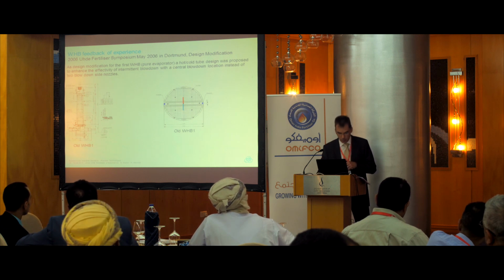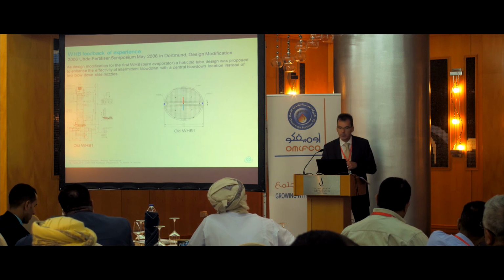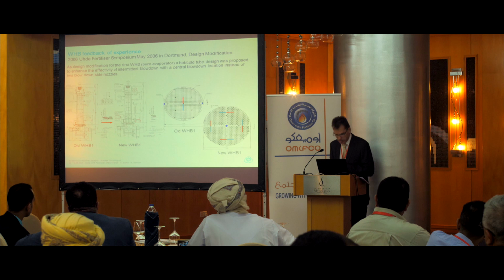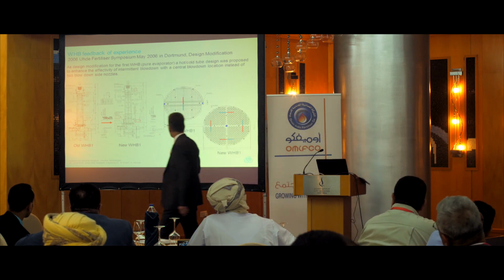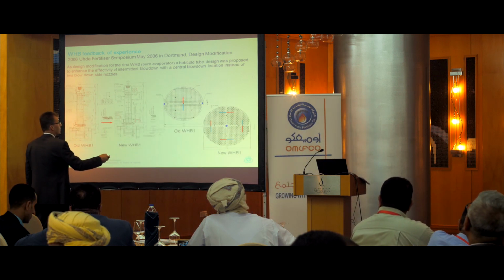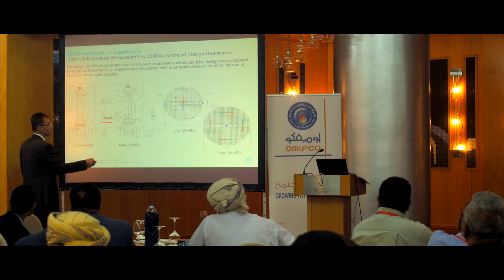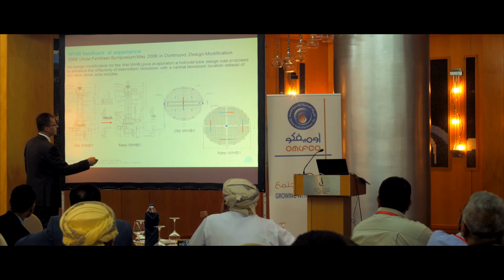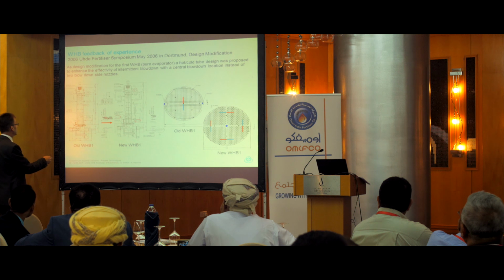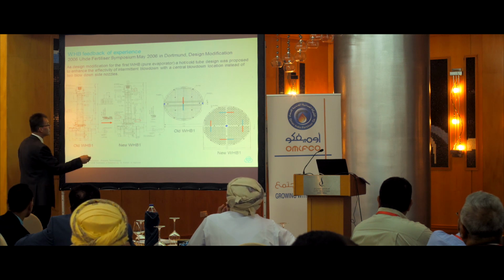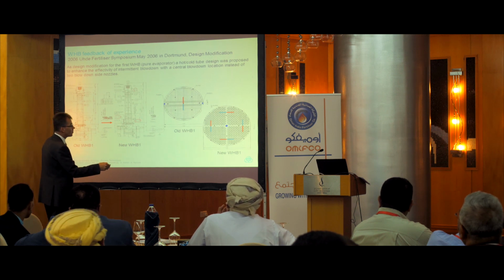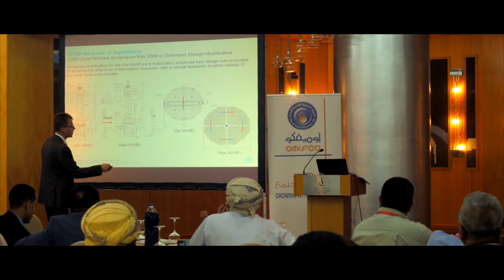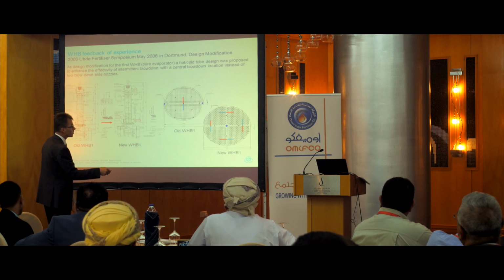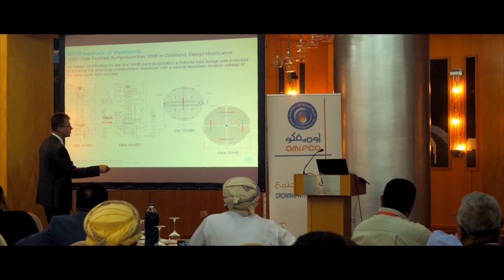Therefore, the standard U-tube boiler was converted into a so-called hot-cold tube design. That means the design before, when you look at the tube sheet: hot side, cold side, simple U-tube. Blowdown was located on the side. Here have been the blowdown nozzles in the older plants. We changed this design to a so-called hot-cold segment design: hot, cold, hot, cold, hot, cold. And we have been able then to put the intermittent blowdown in the waste heat boiler 1 over in the middle.